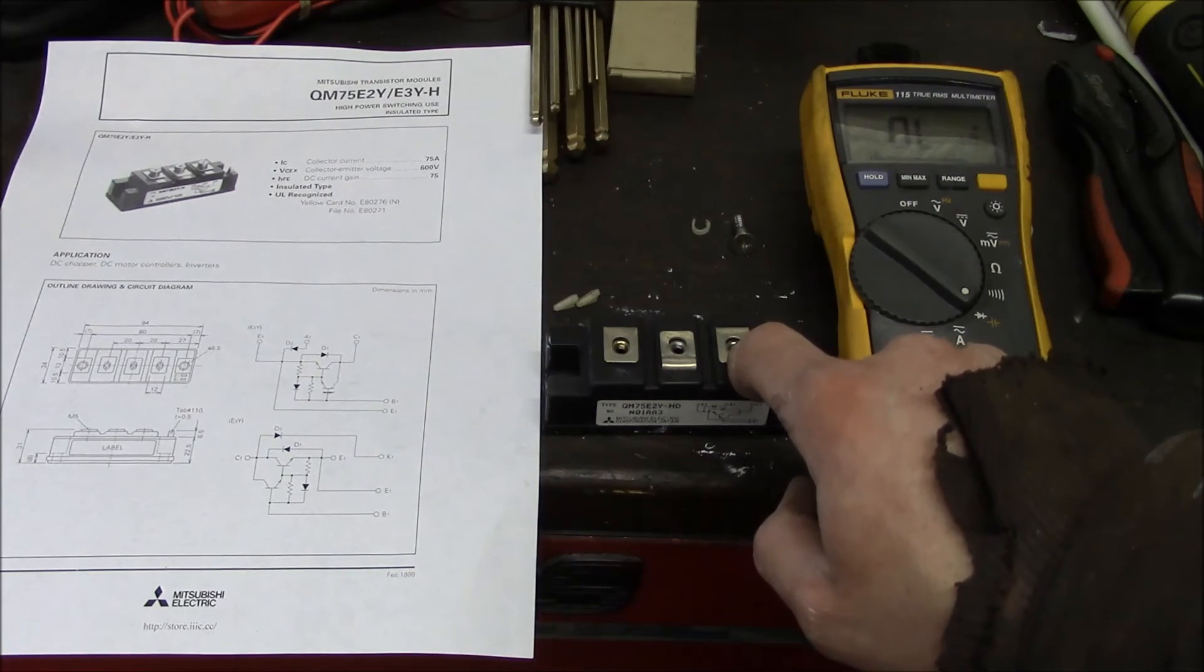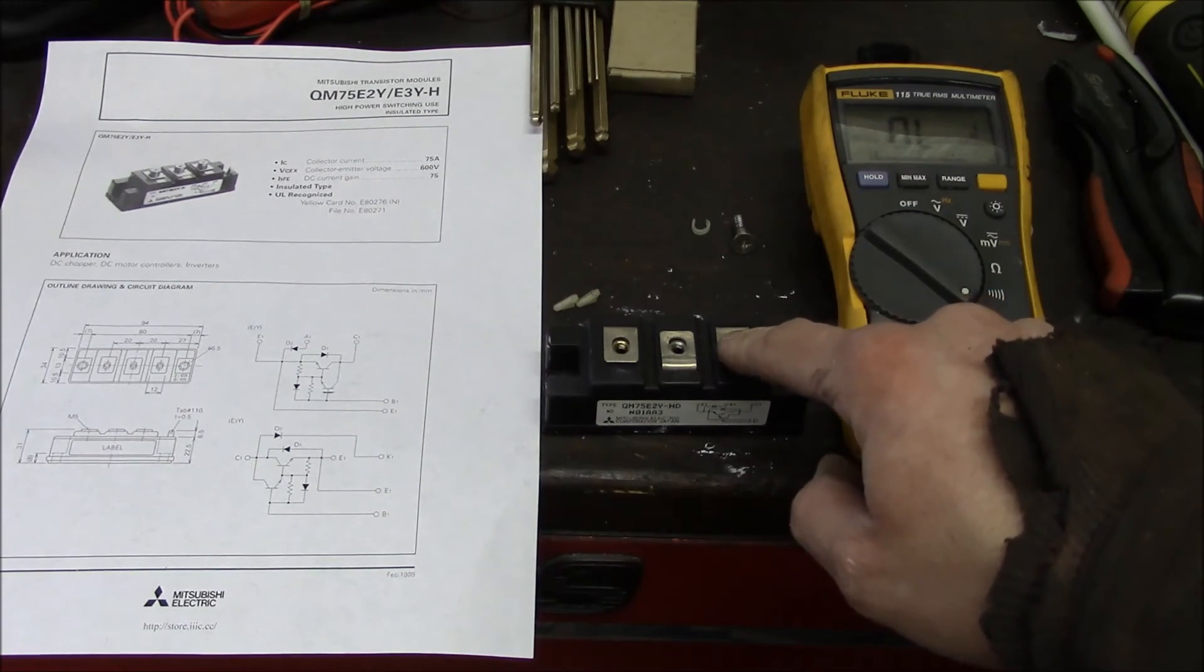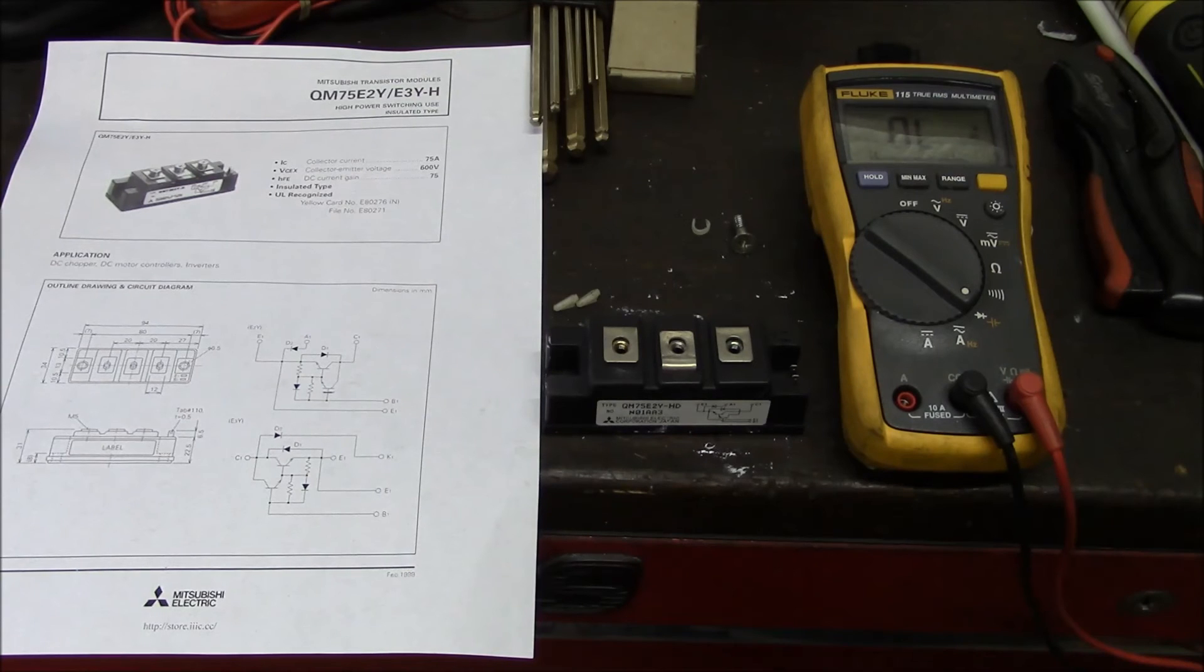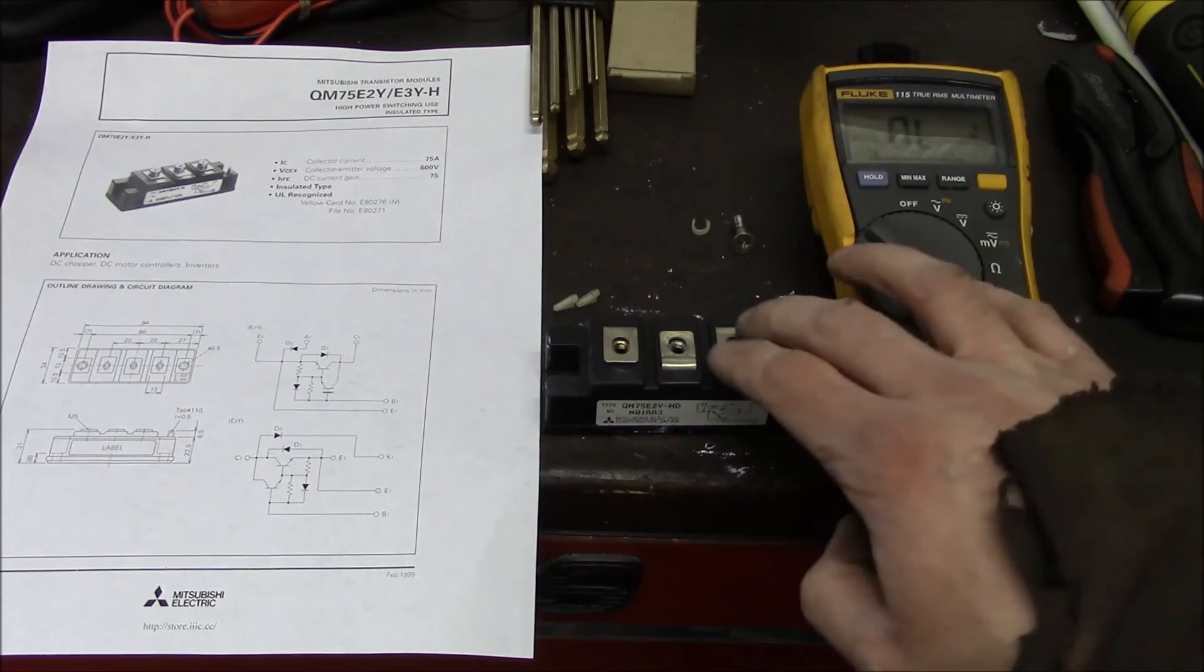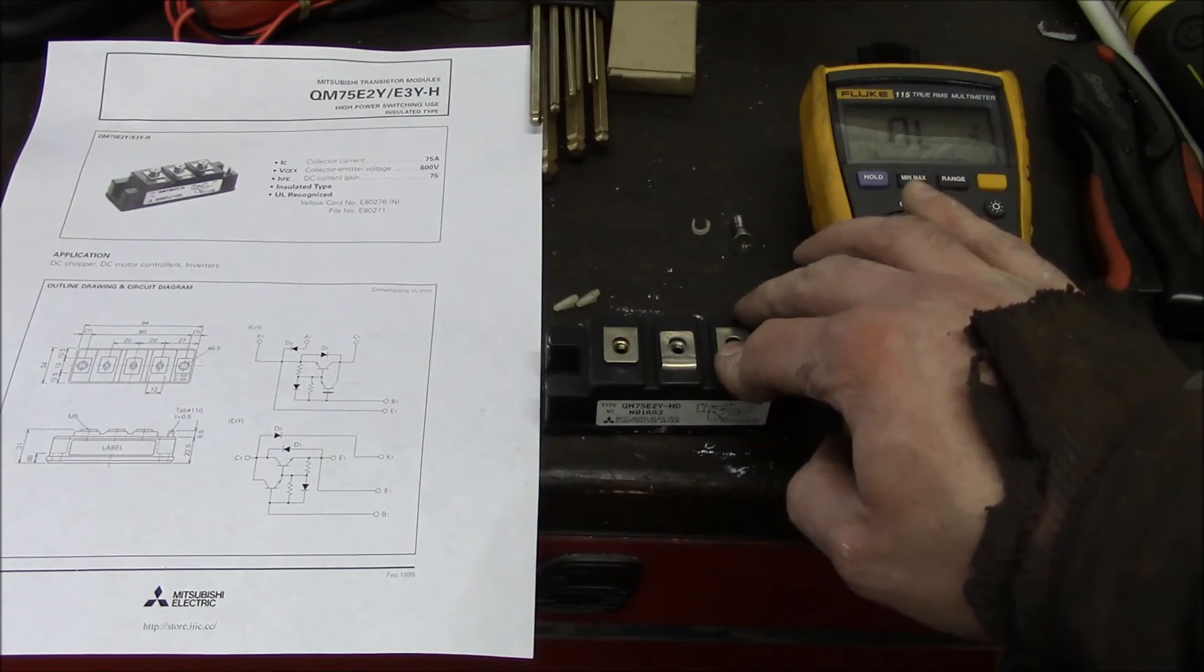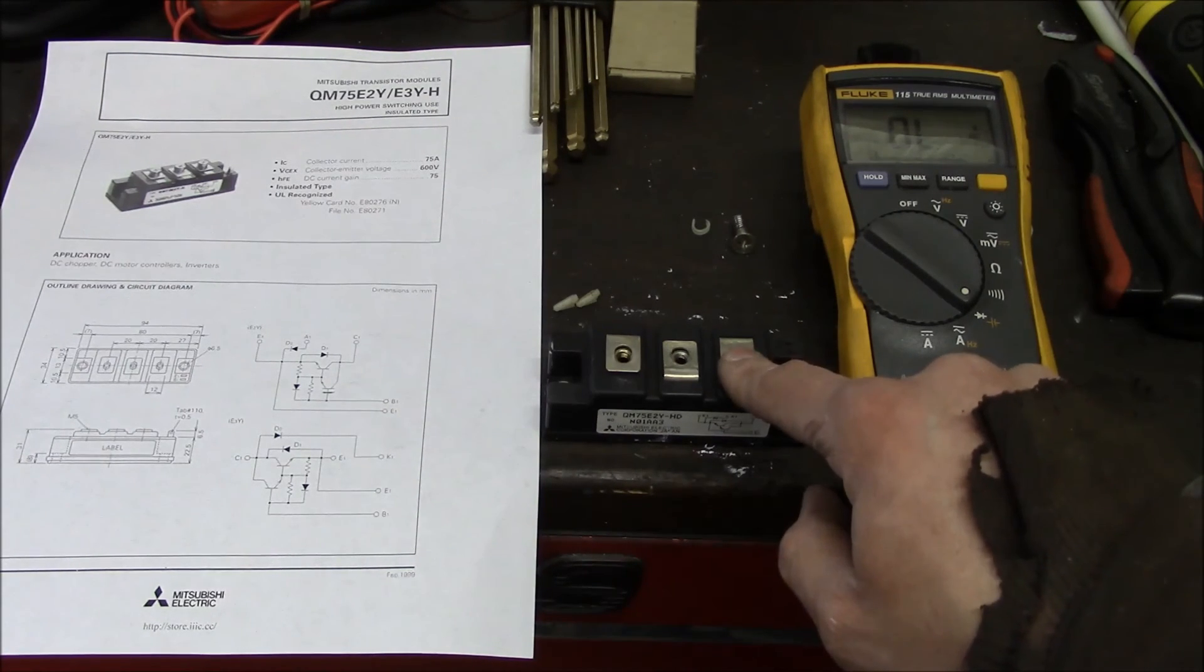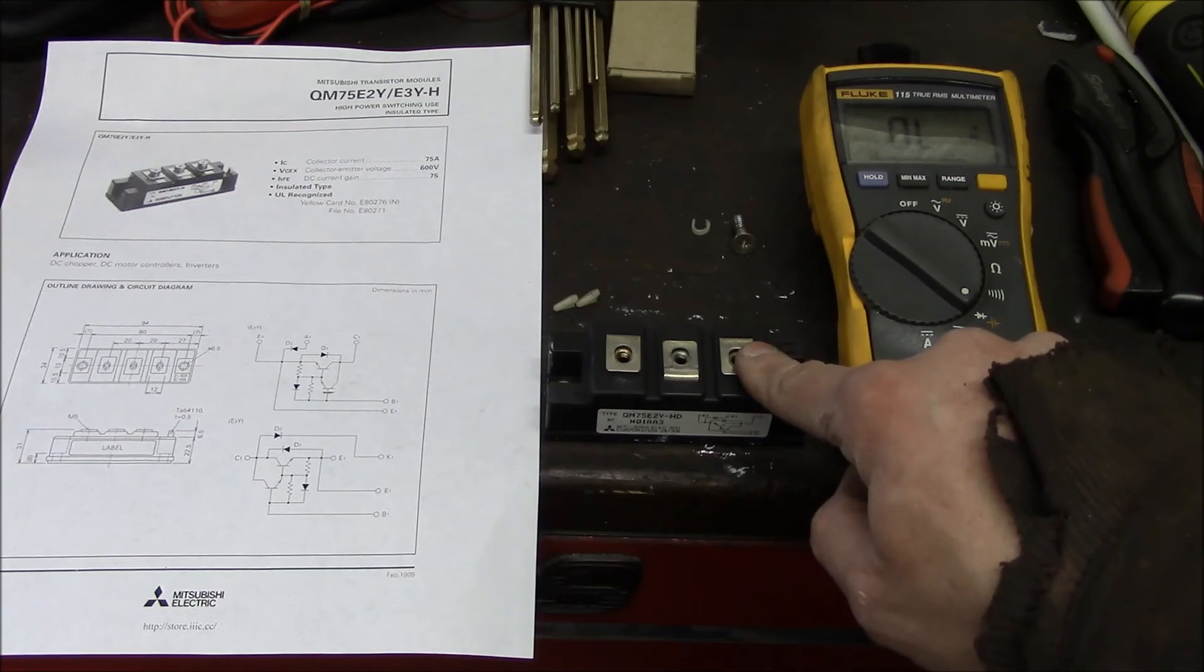So I can put a lot of $50 modules into that spindle drive for $6,700. I'm not an expert about spindle drives or VFDs. But there's really not that much to them. Especially these large industrial spindle drives. They're just made from little components that they bolt together. The real magic is in the computer control side. And that part of the drive is pretty robust. What takes a beating is these big switching transistors. That's where all the amperage is. This little IGBT module is rated to switch 75 amps. So that's a hell of a lot of current to put through this little guy.